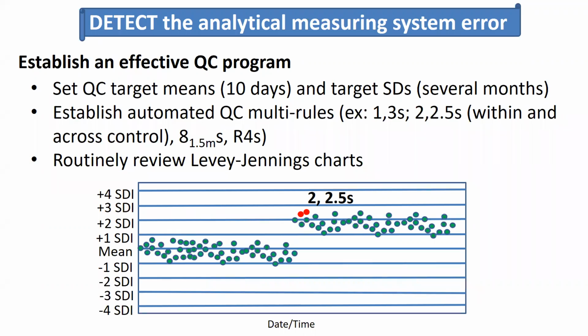QC multi-rules should be established to detect increased random error or imprecision and increased systematic error or shifts in trends. So for example, a set of QC multi-rules might include a 1-3S rule, a 2-2.5S within and across control rule, an 8-1.5S rule where the alert triggers if there are 8 values that exceed 1.5 standard deviations from the mean in a single direction, or a range 4S rule. So this rule will fire when 2 consecutive QC results have 4 SDs or more between them.